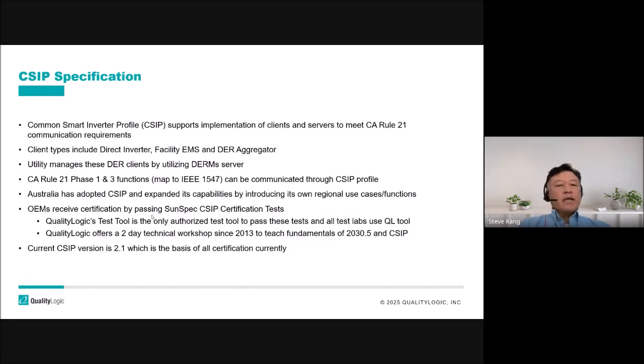Australia has been quite active in the last few years. They originally adopted the CSIP-based standard but expanded its capability because they have different use cases there. For example, they have a solar emergency backstop: in case of too much active power generation from DER devices on the grid, they send a signal for these devices to stop generating power.